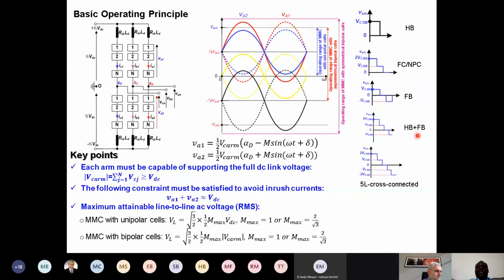While if you have an MMC with bipolar cells, symmetrical or asymmetrical, you break that rule. So the DC voltage can go from the rated value down to 0, and still you can control the active or reactive power between the converter and the AC grid, and the current flow between the converter and the AC grid. And here is a simple example of the voltage across the upper and lower arms. You can see here that the upper arm and lower arm of each phase leg of the MMC operate in a complementary manner, based on these equations.